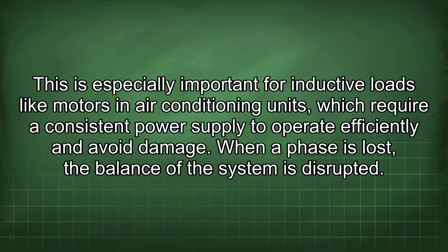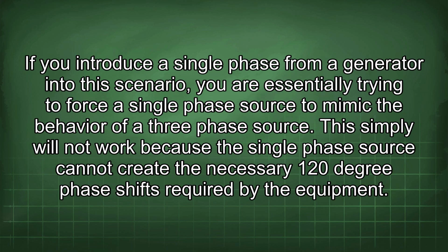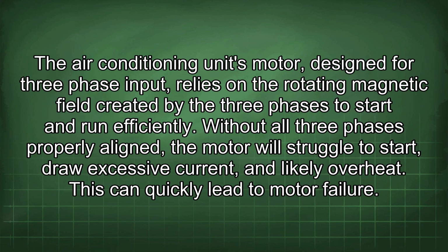When a phase is lost, the balance of the system is disrupted. If you introduce a single phase from a generator into the scenario, you are essentially trying to force a single-phase source to mimic the behavior of a three-phase source. This simply will not work because the single-phase source cannot create the necessary 120-degree phase shifts required by the equipment. The air conditioning unit's motor, designed for three-phase input, relies on the rotating magnetic field created by the three phases to start and run efficiently. Without all three phases properly aligned, the motor will struggle to start, draw excessive current, and likely overheat. This can quickly lead to motor failure.